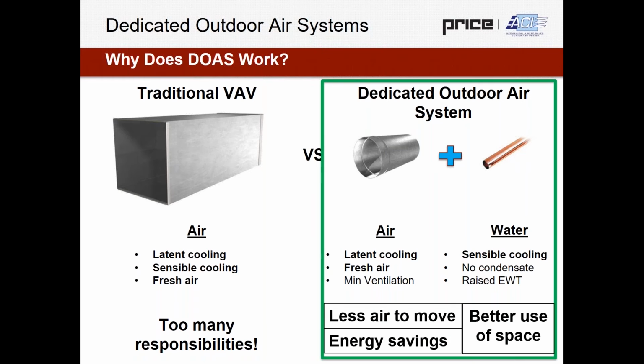The other major reason is water's volumetric heat capacity, which is 3,500 times higher than that of air at sea level. What that really means is an 18 by 18 inch traditional VAV duct, like we see on the left-hand side of the screen, carries the same capacity as a 7-inch round duct and 1-inch water pipe in a dedicated outdoor air system.